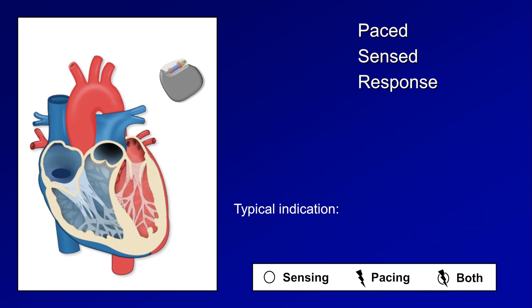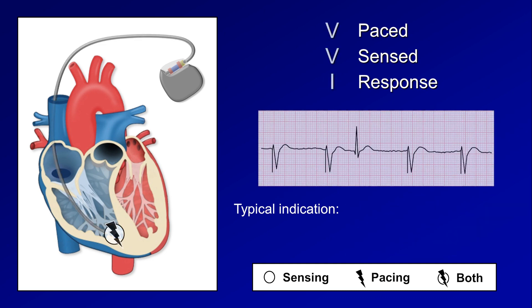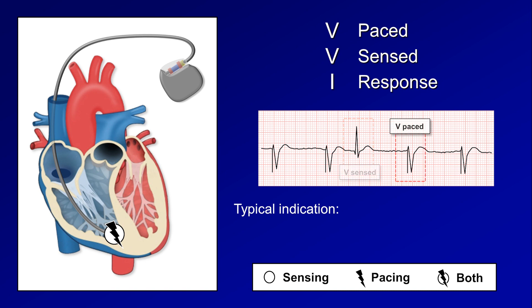The next much more common mode is VVI. In VVI mode, the ventricular lead senses in addition to pacing, and when it senses an intrinsic QRS complex, the response is to inhibit pacing — hence the I. So this narrow QRS complex has been normally conducted through the heart's intrinsic conduction system, the ventricular lead senses this, and therefore doesn't pace right away. But after a duration of time without sensing another intrinsic complex, it does go ahead and pace.